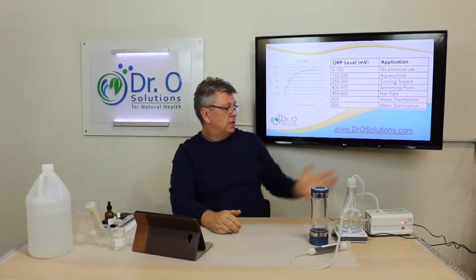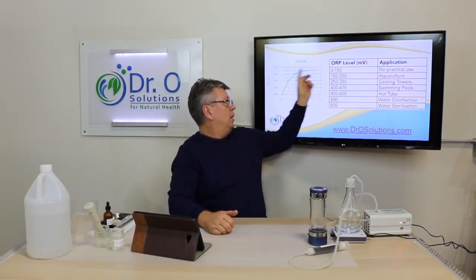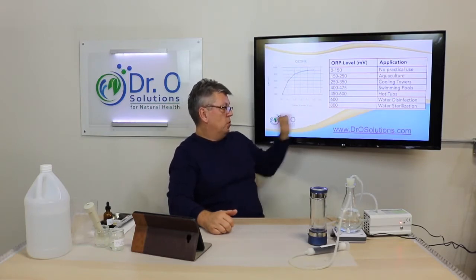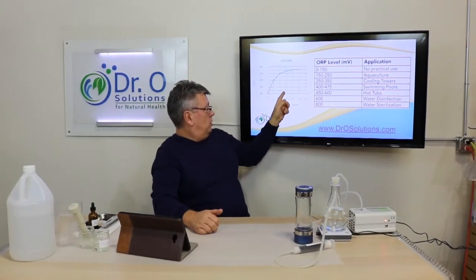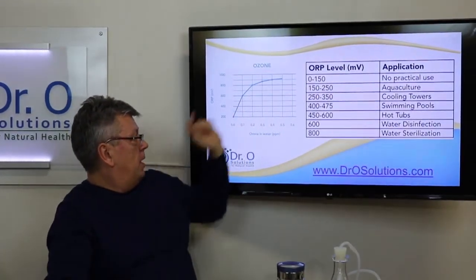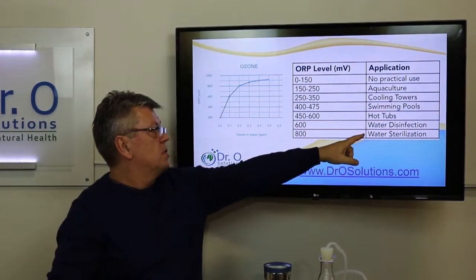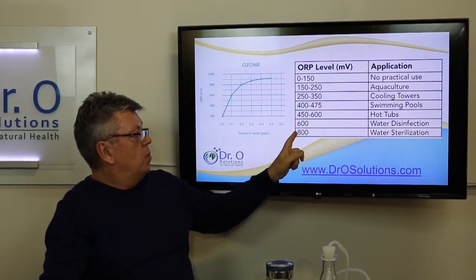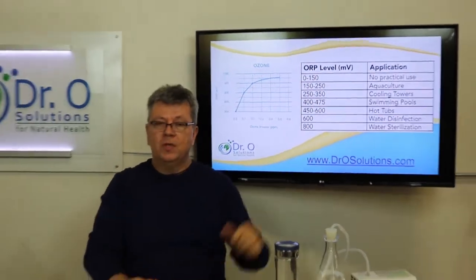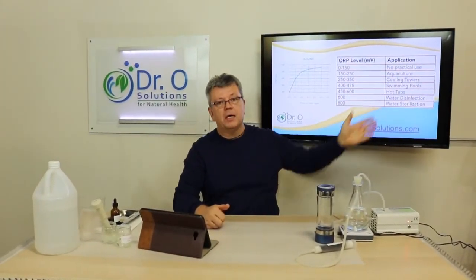Here is an example application of ozone. Ozone has a very high oxidative reaction to all substances. Here is ORP referenced to PPM ozone in water. When we get to 0.3 ppm, we cross 900 ORP. Disinfection starts at 600 ORP, and when we get to 800, that's sterilization. That's how ozone applies to processes used in commercial applications.